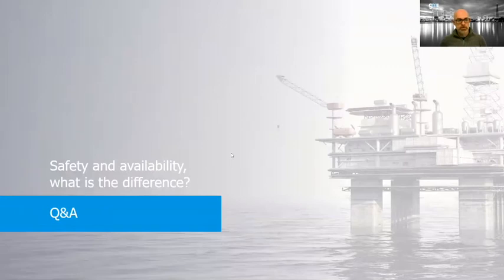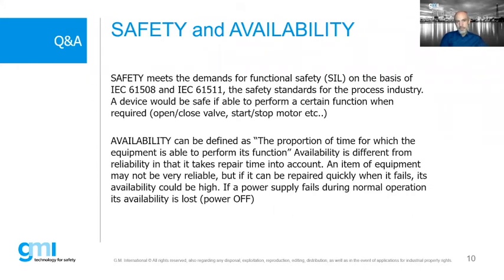Next one: often we are asked what the difference is between safety and availability. Yes, very important. We have already discussed that. Safety is the only parameter that functional safety of the SIL is looking at. It is based on IEC 61508 and IEC 61511. The first is for manufacturers, the second is for users. It is the safety standard for process industries. A device, to be safe, is able to do something. Basically applications are opening or closing a valve, starting or stopping a motor. That is the function required.